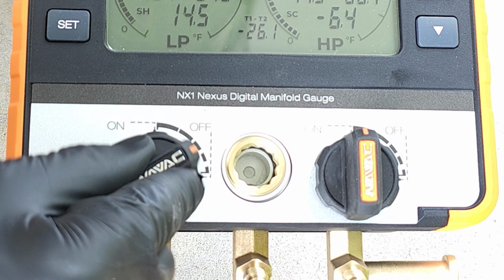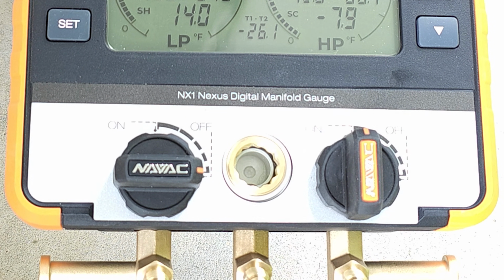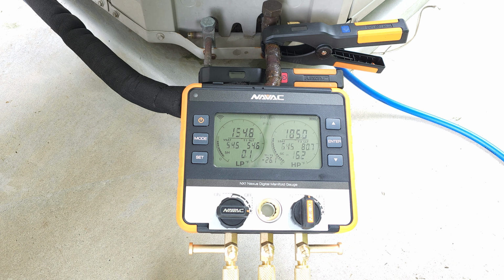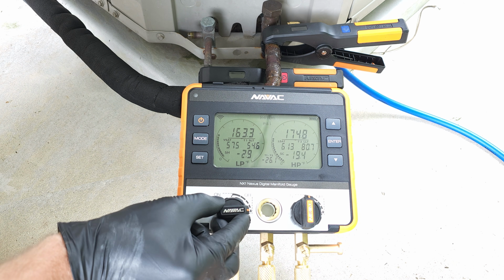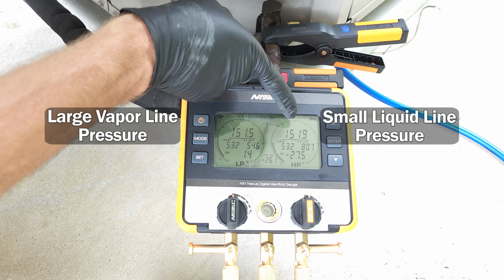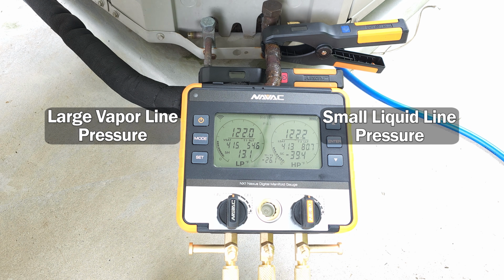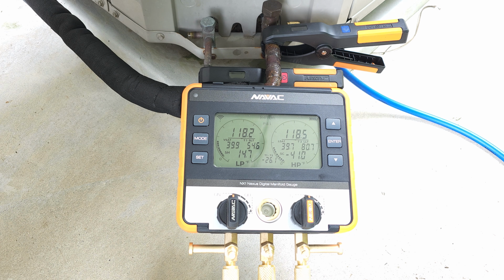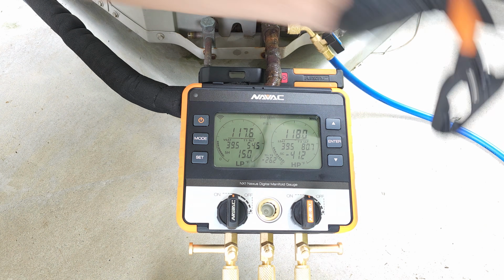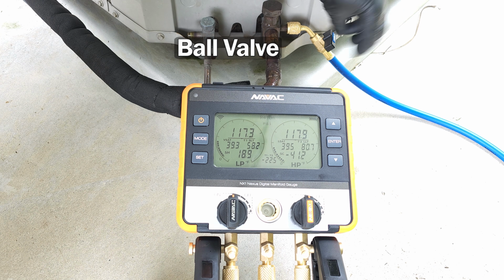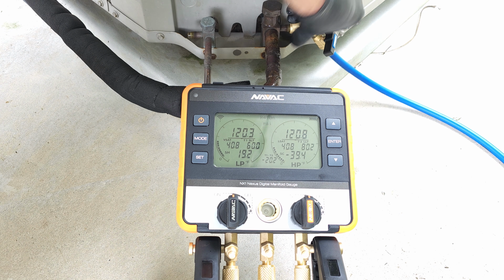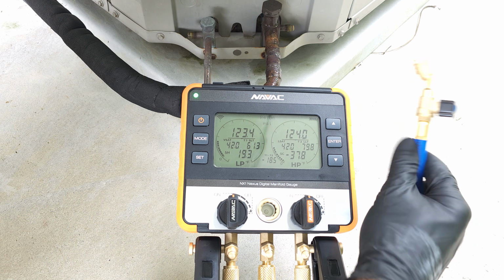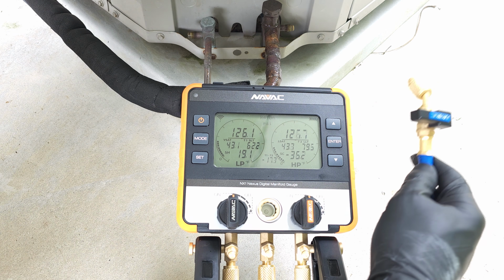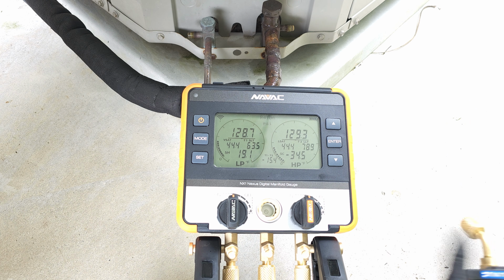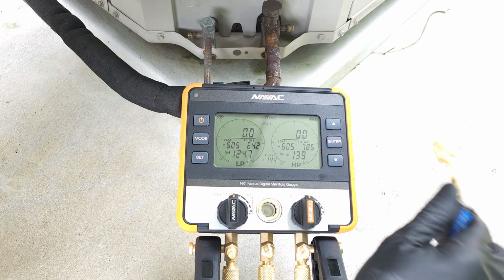You can see your liquid flashing right here in the sight glass. There's liquid refrigerant and oil there. We're going to want to do this until basically the pressure over here matches the same pressure as over here. And so we're good. So after that, we can go ahead and disconnect our clamp. I'm going to shut this ball valve off right there, disconnect right here. And then all you have left is just a little bit of vapor in the manifold and hoses, which falls under the de minimis rule. So that's it. That's all it is. It's not much at all.